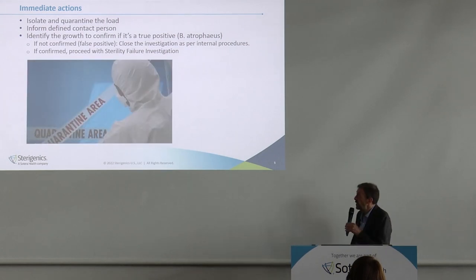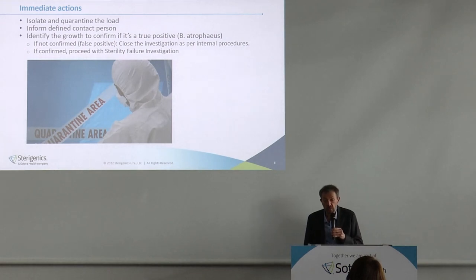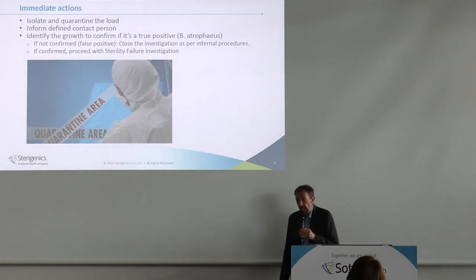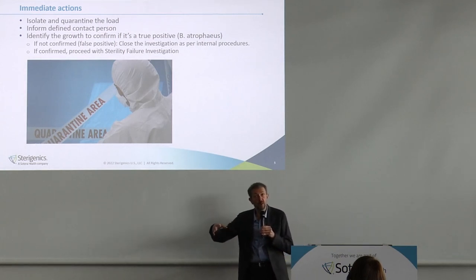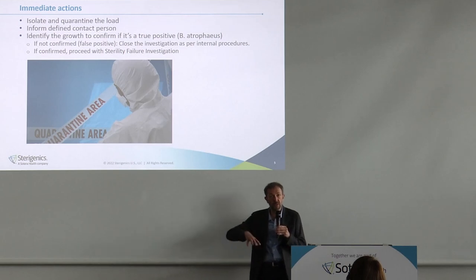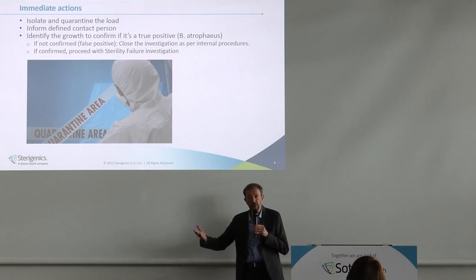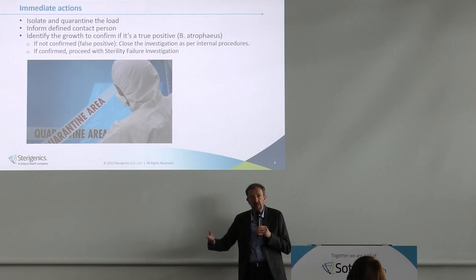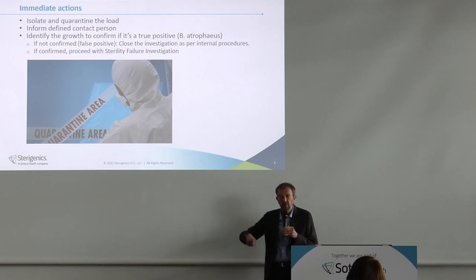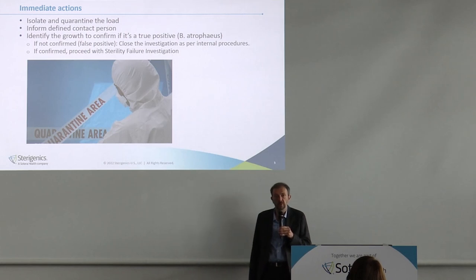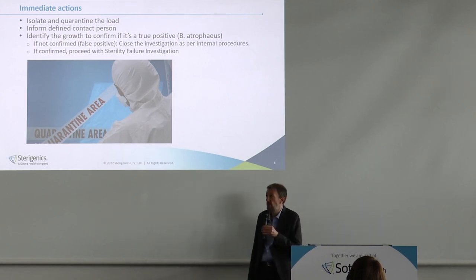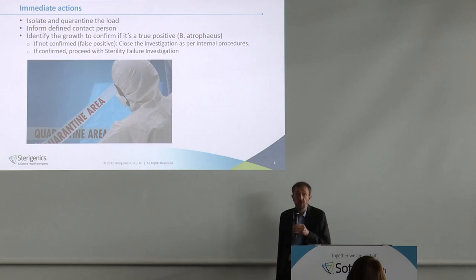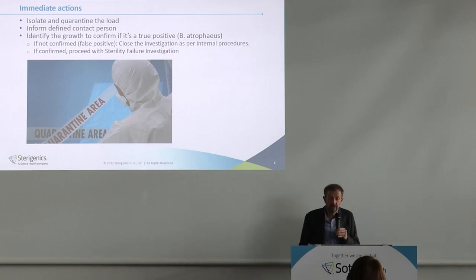Isolation of the load is key and essential. In some cases customers pick up the load before final release to speed up time to market, so they may already have the load in their premises waiting for the certificate of biological indicator. If we don't inform them, the likelihood of the load being distributed is quite significant. That's why this communication must go straight to the customer so there is a proper isolation and quarantine of the load.